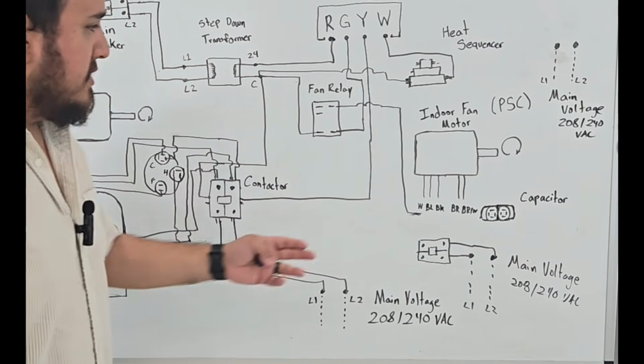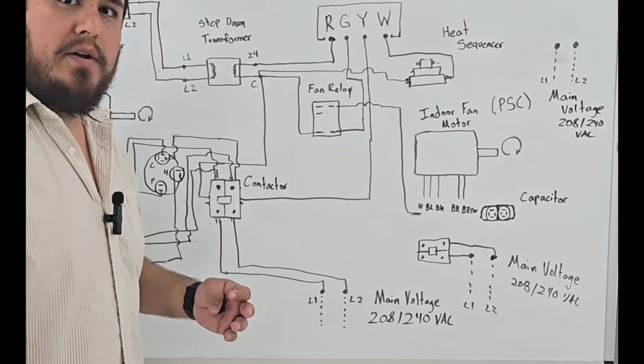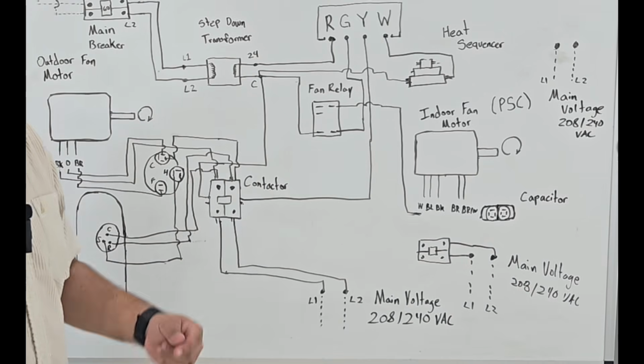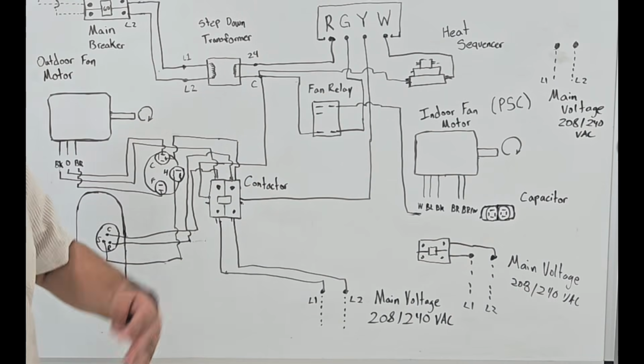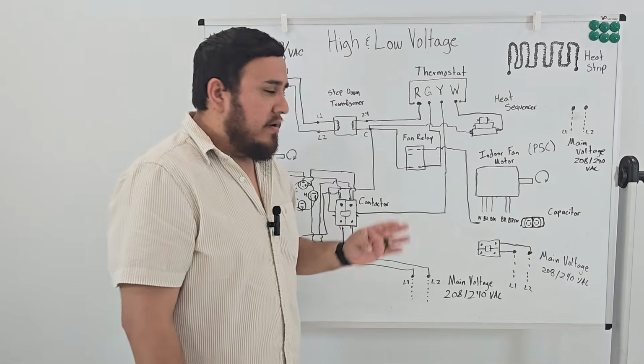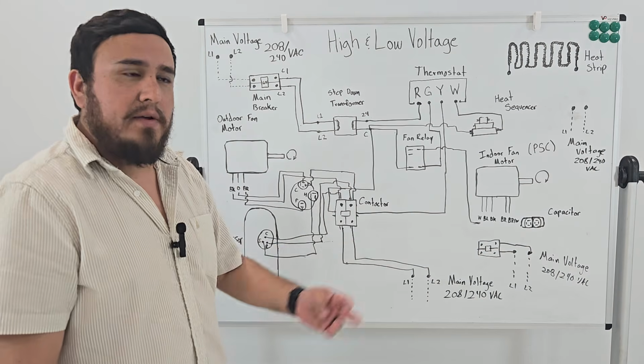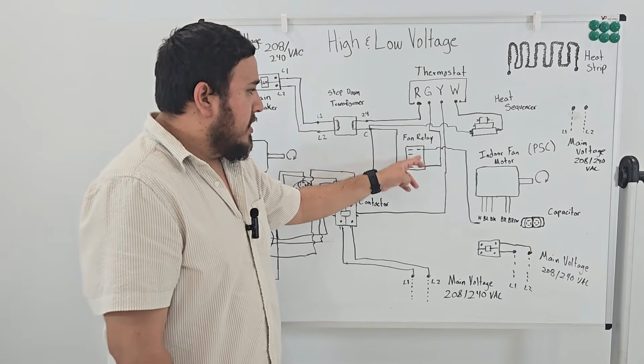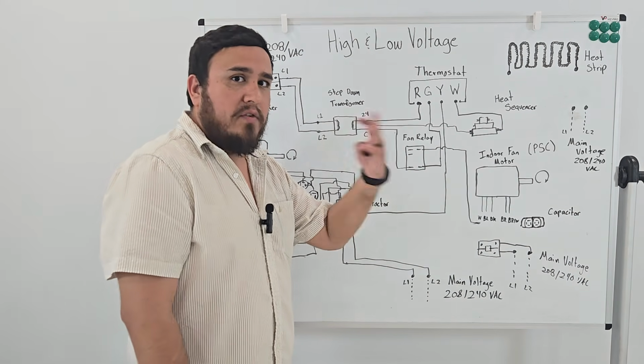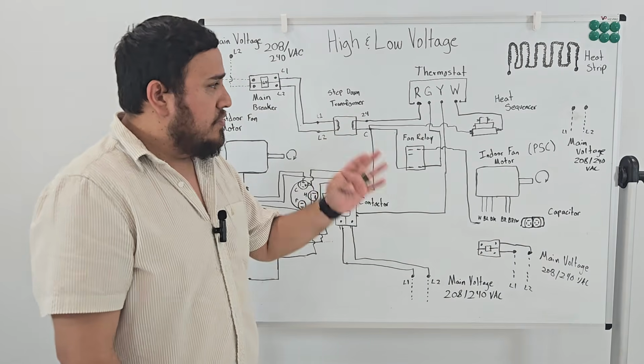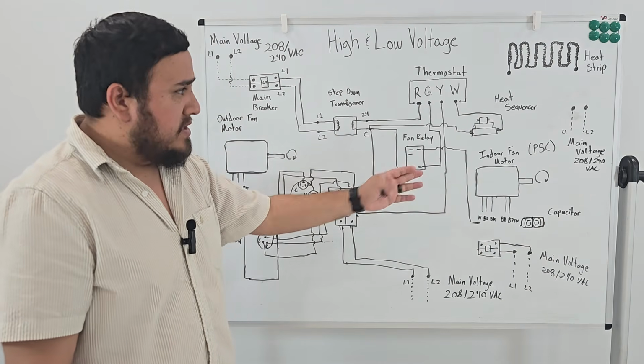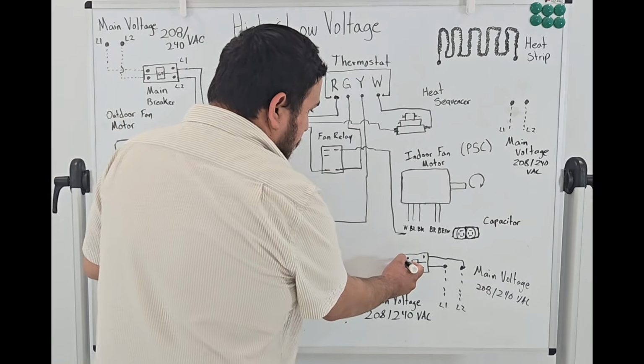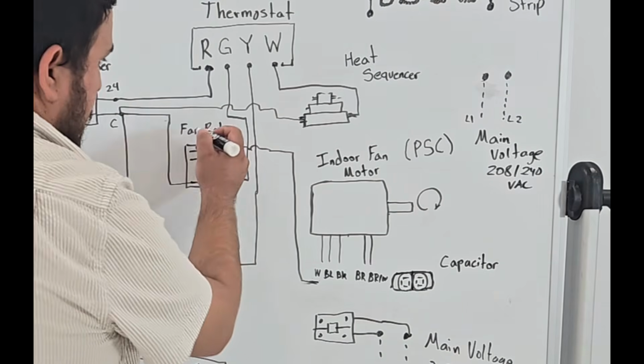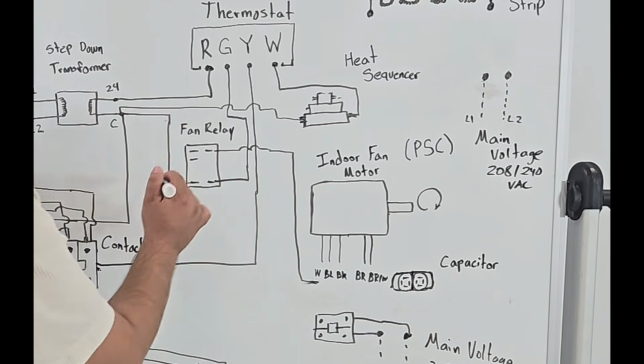After setting it to the fan relay, I'm going to connect the other side of the fan relay to my main voltage. Remember, these controls are there to control your high voltage. So I'm going to control the common wire, or one of the lines to my loads, in this case my indoor fan motor, by bringing line voltage over to the other side of my fan relay.